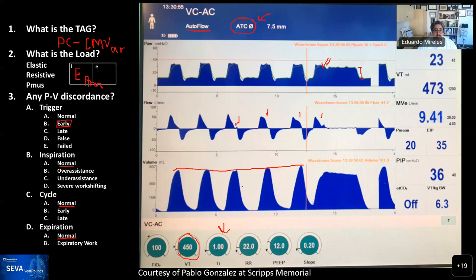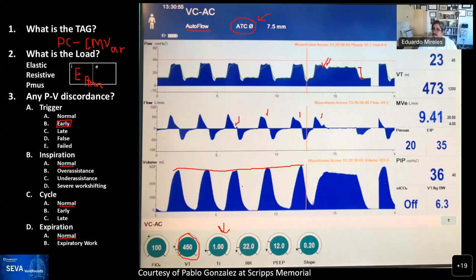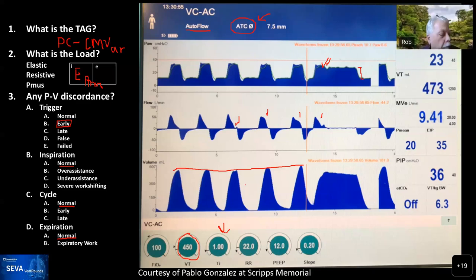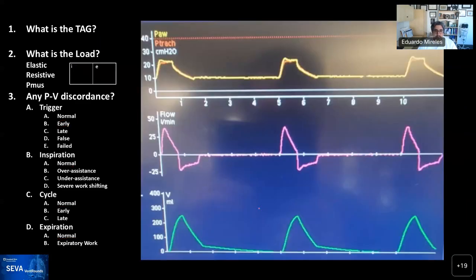Years ago I did a study on Draeger ventilators and discovered that allowing ATC on top of PAV is not a good idea — that would be like double dipping, and it's found to be problematic. Thanks to Pablo for sharing this really cool image. Please send us as many waveforms as you want.